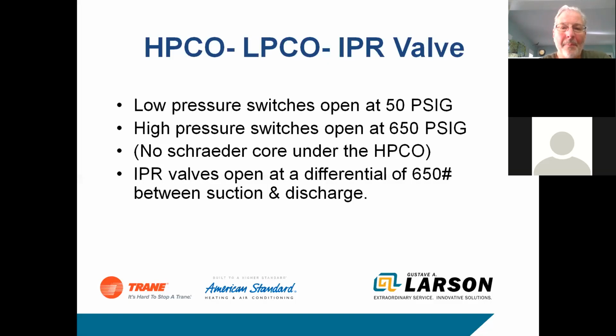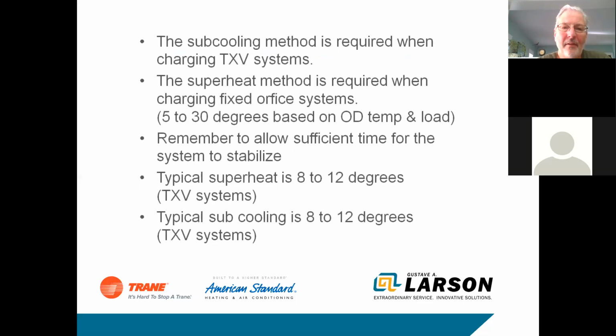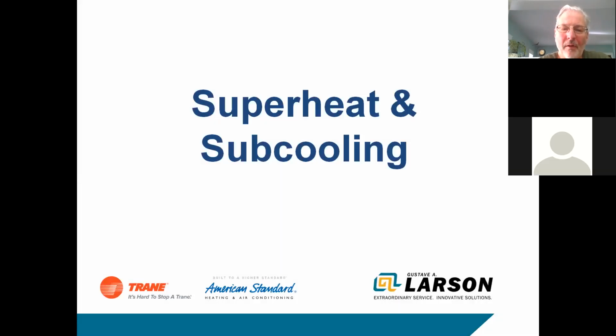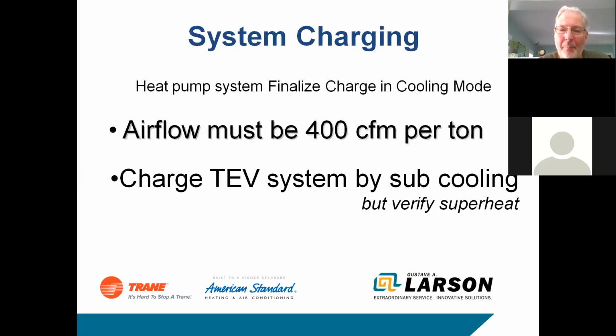So if you want to see if you're properly charged, and I'm going to jump ahead here again, guys. On a TXV system, we charge by subcool. On a non-TXV system, we charge by superheat, okay? Typical superheat is 8 to 12. Typical superheat or subcool is 8 to 12. All right. We must be at 400 CFM per ton. In other words, make sure we've got good airflow through the system.